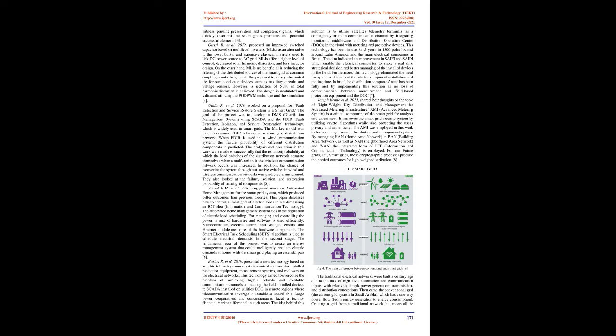The idea behind this solution is to utilize satellites' telemetry terminals as a contingency or main communication channel by integrating monitoring middleware and distribution operation center, DOC, in the cloud with metering and protective devices. This technology has been in use for 5 years in 1,500 points located around Latin America and the main electrical companies in Brazil. The data indicated an improvement in SAIFI and SAIDI, which enable the electrical companies to make real-time strategic decisions and better manage the installed devices in the field.